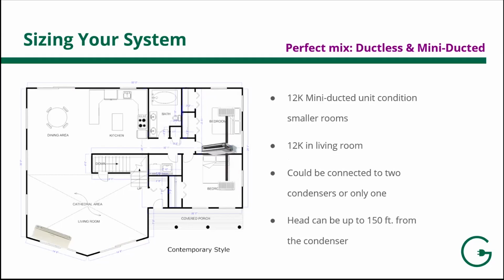Now, you might be wondering what a potential solution for small bedrooms that are adjacent to each other would be. One solution is a mini ducted system where you put an air handler in the attic above or the basement below these rooms, and you put tiny 3 to 6 foot ductwork or refrigerant lines into each room. In this illustration, you've got 12K British thermal units that are split between the 2 back bedrooms. And so each bedroom is getting 6K British thermal units and are nice and comfortable.